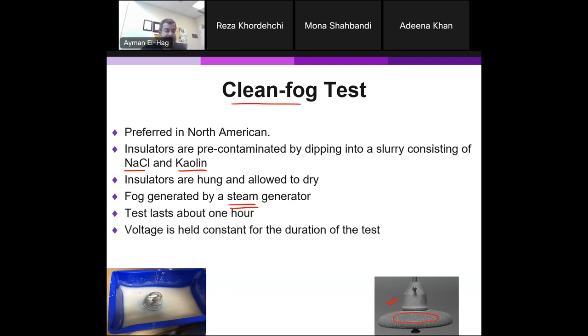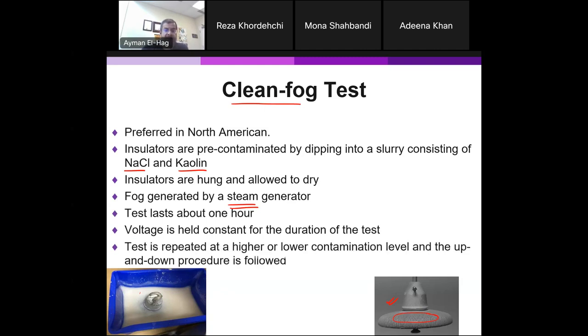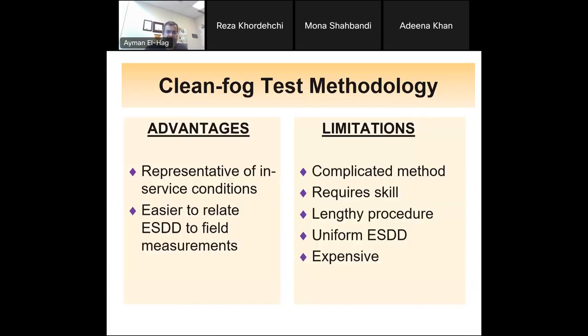Now the voltage is constant. If the system withstands, or flashes over, we either add more or less contamination, the same way as the up and down procedure mentioned before.